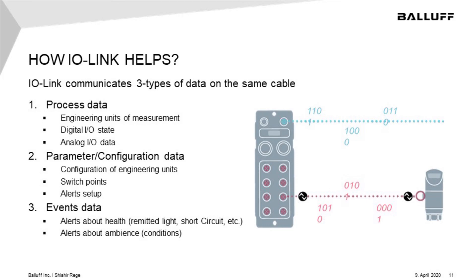IO-Link offers three types of data on the same cable. First is process data — the primary purpose of that sensor and what it needs to provide for the process. Second is parameter or configuration data, where you can set ambient conditions, switching points, alerts, or even calibration data. Third is events data, where the sensor, after detecting an abnormal condition, fires a signal to let the PLC or controller know through the master that something is wrong. This makes IO-Link even more suitable for diagnostic-ready technologies.